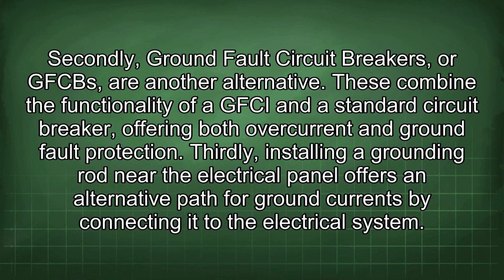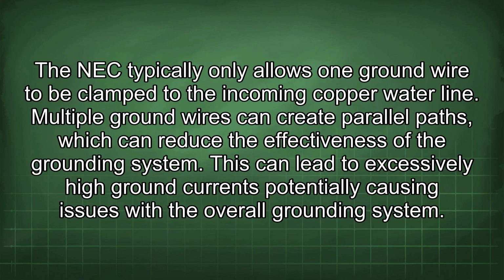Thirdly, installing a grounding rod near the electrical panel offers an alternative path for ground currents by connecting it to the electrical system. The NEC typically only allows one ground wire to be clamped to the incoming copper water line. Multiple ground wires can create parallel paths, which can reduce the effectiveness of the grounding system. This can lead to excessively high ground currents, potentially causing issues with the overall grounding system.